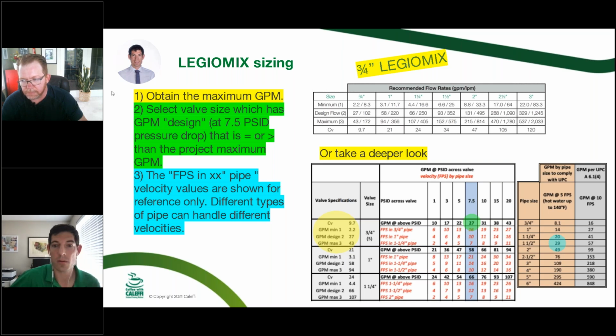And that comes up a little bit in the balancing too. But you do not want to be sending hot chlorinated water through any piping material at 10 feet per second all the time. Your recirc pump is going to be oversized if that's the case. You risk pinhole leaks through the copper.